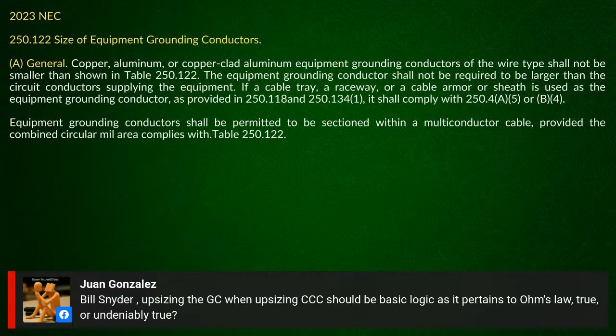Now, one of the things that I looked at, and Bill actually asked me this one, is when they were saying you've got to go up in the equipment grounding conductor size based on the overcurrent device. I saw some of that, and I was like, no. If you actually look at 250.122(A), what does it say in the second sentence? It says the equipment grounding conductor shall not be required to be larger than the circuit conductors supplying the equipment. So in your example there, if I'm running number 12s over there, I don't have to be any larger than a number 12 on my equipment ground.